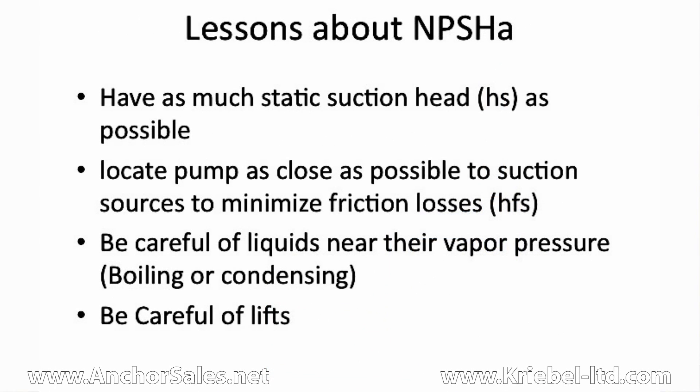So let's review some lessons learned. Always have as much static head as possible. Locate the pump as close as possible to the suction source to minimize suction friction losses. Be careful of liquids near their boiling point — this includes all boiling and condensing applications. And be careful of lifts. Using this information will keep you out of problems when you're designing pumping systems. And if you need help, you can always contact us. Thanks for listening.